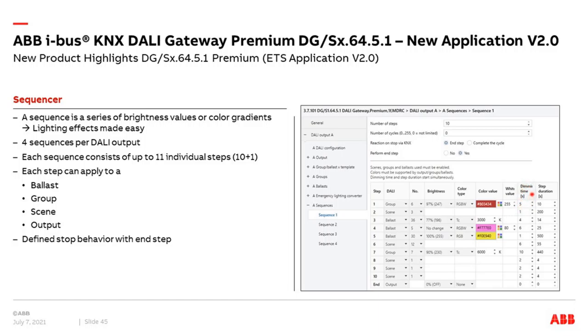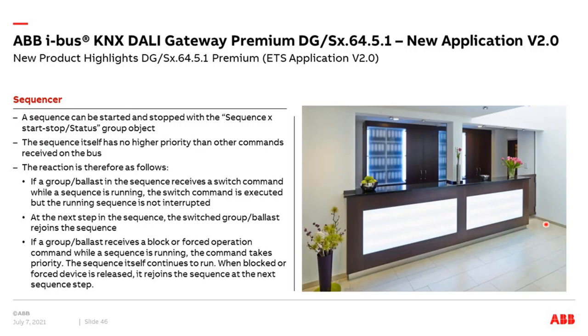The step duration determines how long a step stays active. You can enter a time between 0 and 65,535 seconds. The scene starts immediately and at the same time — for example after 10 seconds the next step begins, then after 200 seconds the next step, then after 40 seconds the next. Each of the four sequencers can be stopped and started via a 1-bit object, and there is also a status group object showing whether the sequencer is active or not.